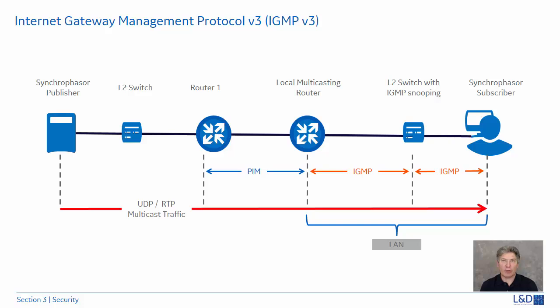Source filtering allows the routers to select the appropriate path to deliver the multicast instead of delivering to all possible paths. IGMP version 3 is used on both IP version 4 and IP version 6 networks, and it operates within the substation's LAN to the local router observing the IGMP traffic.